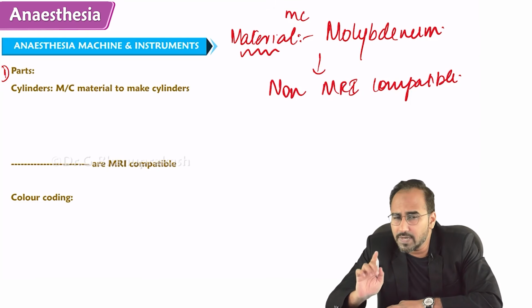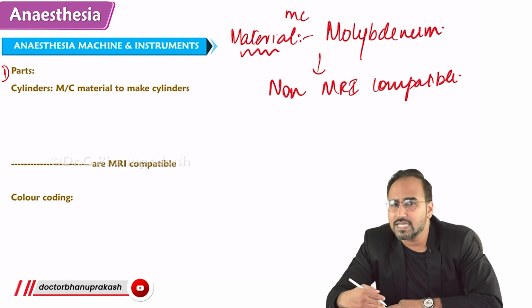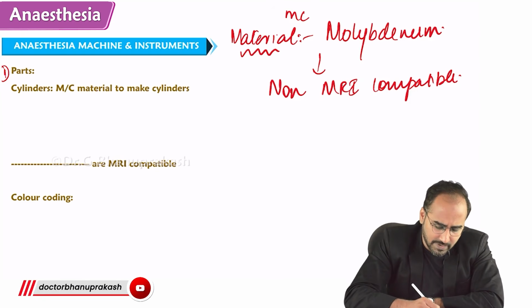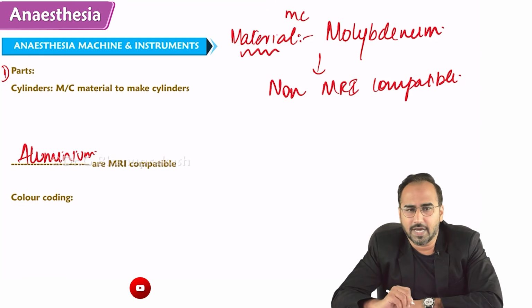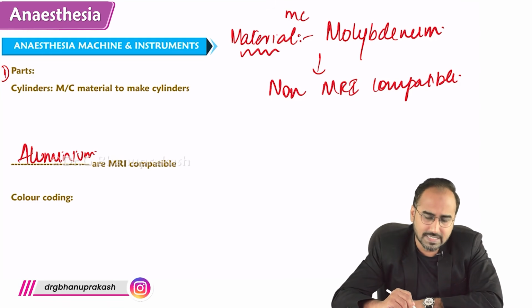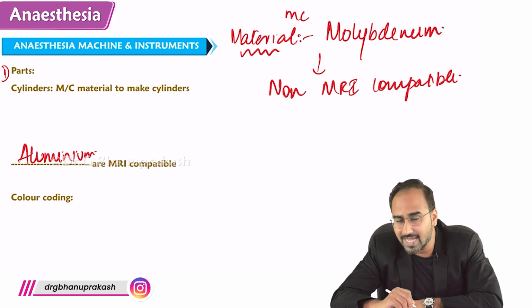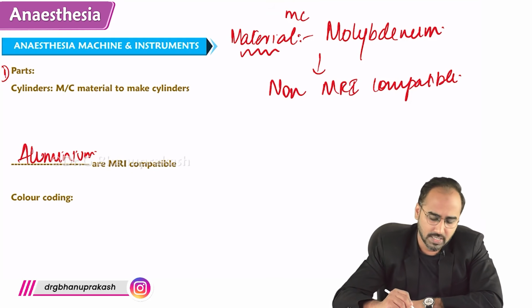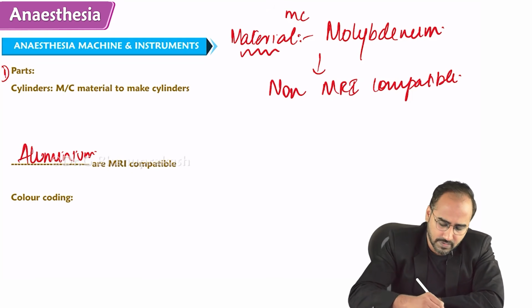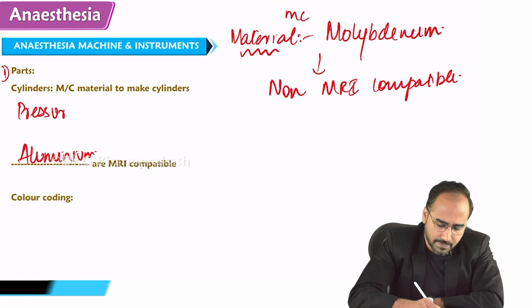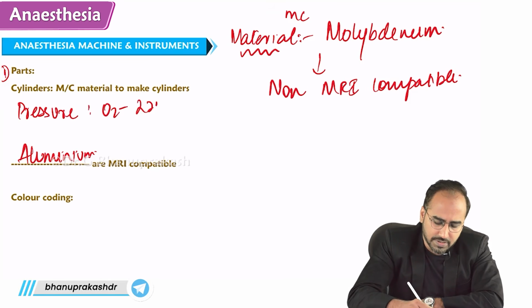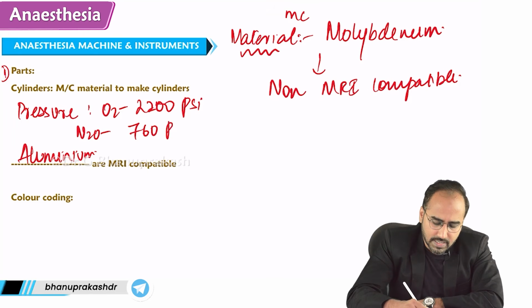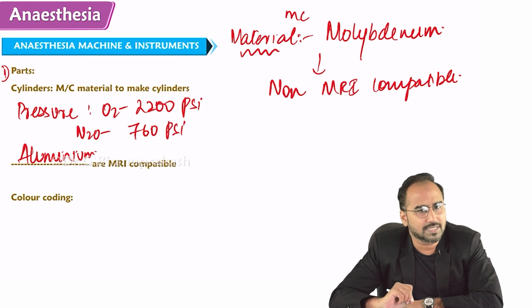So you need to understand, guys, molybdenum cylinders are non-MRI compatible, but nowadays we have cylinders made up of aluminium which are MRI compatible. Right? Now, what else we need to remember, guys? I also told you the cylinders are storing the gases. Non-volatile gases are being stored in the cylinders at a good pressure. What is the pressure inside the oxygen cylinder? The pressure inside the oxygen cylinder is 2200 psi, whereas the pressure inside the nitrous cylinder is 760 psi, 760 per square inch.